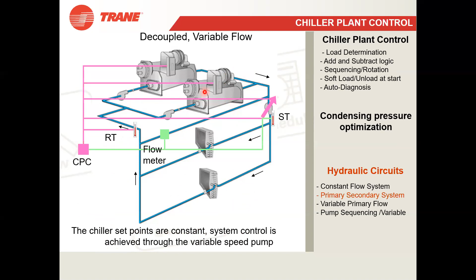And variable speed pump control from differential pressure in the secondary circuit, that I have already told, that you can control the speed of the secondary pump. And chillers and pumps are sequenced by bypass flow or water temperature. Yes, so the excess water will go through this bypass line, going back to the main lines. So I hope everybody has understood that.